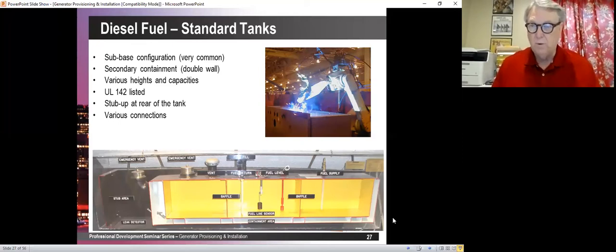This is a tank on the bottom. I think this is wonderful because you're not going to get to see this when your tank gets to the field. On the end here is your conduit opening. Here's your emergency vents. Those are options. They are only required on legally required or emergency generators. They're in case the tank explodes. Those blow off and prevent the tank from rupturing. Here's your normal vent that allows it to breathe, your fuel fill, your fuel return. Here's your fuel levels. And inside, you can see that we have baffles that prevent sloshing to some degree.